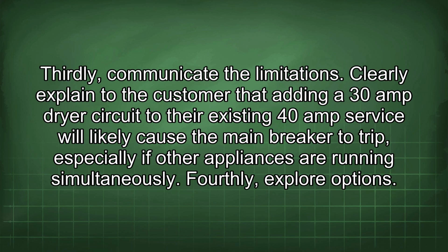Thirdly, communicate the limitations. Clearly explain to the customer that adding a 30 amp dryer circuit to their existing 40 amp service will likely cause the main breaker to trip, especially if other appliances are running simultaneously.